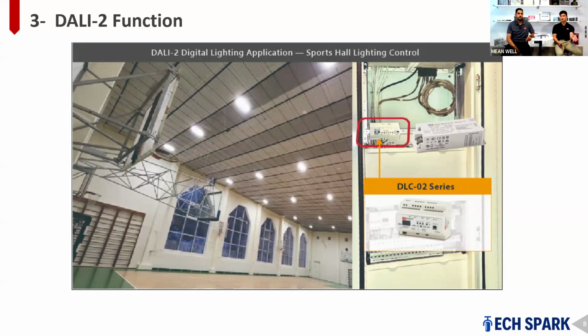Why should I choose DALI control over 3-in-1 dimming? That's a good question. The choice depends on how many lights you need to dim or control. If you're controlling a big building with 100 or 200 lights, you'll definitely go with DALI. If it's just a small number of lights, like 5, 10, or 20, it's easier to go with 3-in-1.